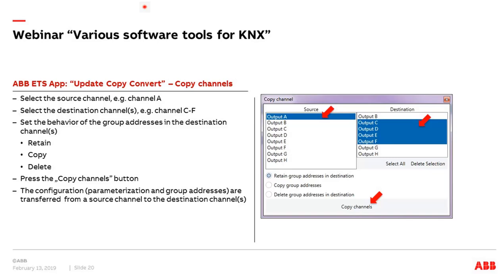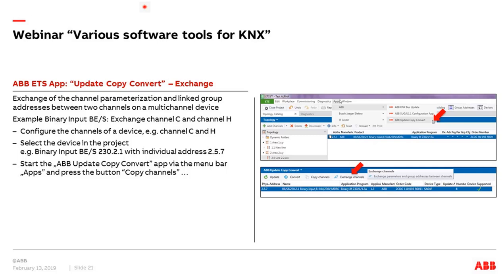Exchanging channels within one product is also possible. Example with a binary input: due to wrong wiring in the distribution board we don't want to rewire, so we change the channels in the application — for example channel C with channel H. Select the device, click exchange channels in the app, specify which channels to swap along with group address options, and press the button. Very simple but quite useful when you can't easily access components to change wiring.